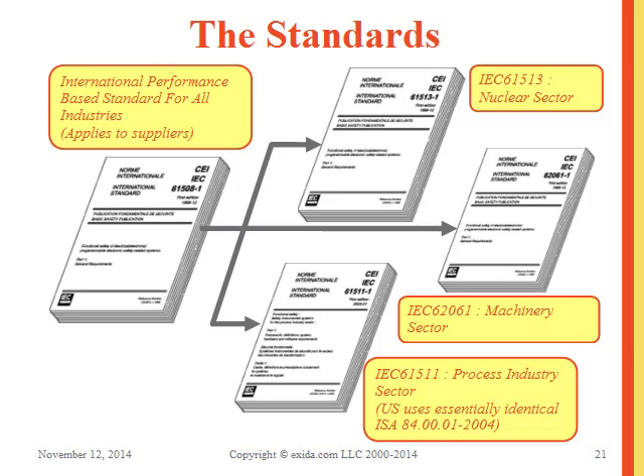IEC 61508 is commonly referred to as the umbrella standard — it applies to all industries and mostly to suppliers. It was broken into multiple sector-specific standards: the nuclear section is 61513, the machinery sector is 62061, and the process industry sector is 61511, which we'll dive into more today.